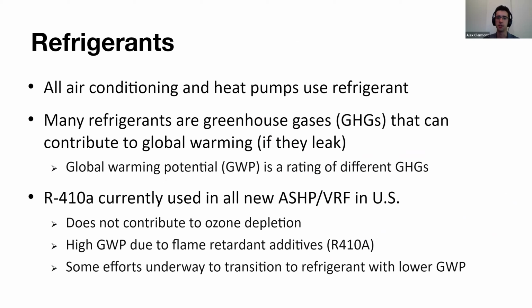Now, R410A is actually used in all new air source heat pumps and VRF in the US, with an exception, which we'll talk about in a minute. Now, R410A does not contribute to ozone depletion. You might remember the days of R22, which was actually phased down in the 90s and 2000s and then officially phased out. And as of January 2020, R22 can no longer be imported or manufactured. This was actually due to the ozone depletion of R22. Now, it's still possible to buy recycled R22, which has been reclaimed from existing equipment, or to buy drop-ins, such as Bluon, which is R458A. Now, the phase out of R22 is actually one of the most successful global treaties.